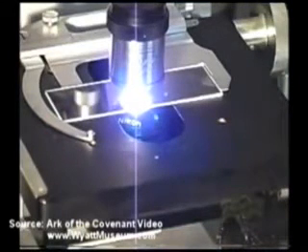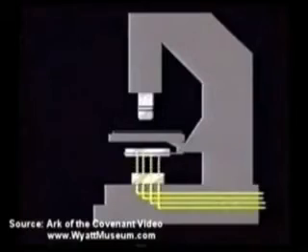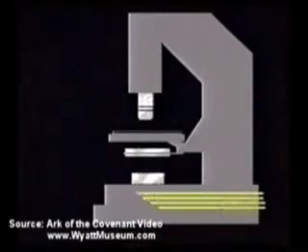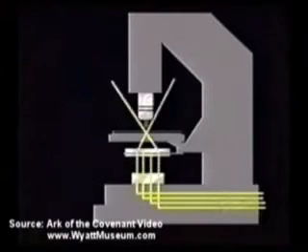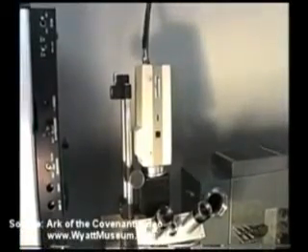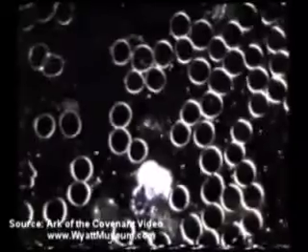The microscope employs an extremely bright xenon or mercury light source, which can be combined with tungsten light. The light is directed across the microscopic specimen rather than on or through it in what is known as a dark field configuration. The light reflecting off the object is transmitted through the microscope and is magnified over 1,000 times. The image is then captured by a sensitive CCD camera and transmitted to a monitor for viewing at screen magnifications of up to 30,000x. Under these conditions, the tiny living particles can plainly be seen against a dark background.